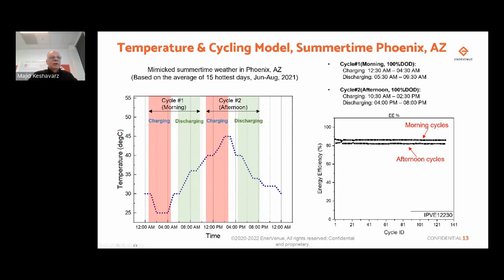One of them is charged in the peak of the heat, and the result is shown on the right-hand side. It's pretty consistent, very flat performance. Obviously, the morning cycle and afternoon cycle are a little bit different in efficiency, but that's what the utility companies like to see so they can do their calculations, return of investment. This can tell you exactly what they should expect. And most importantly, we are not using any HVAC or anything. This is ambient temperature fluctuating, going as high as 46 degrees in the afternoon in Phoenix.